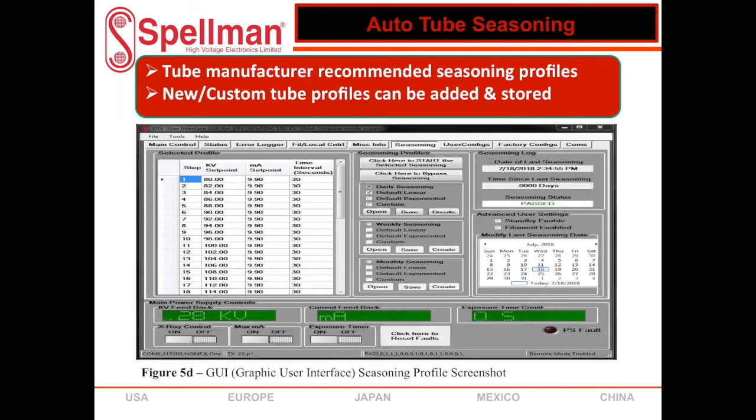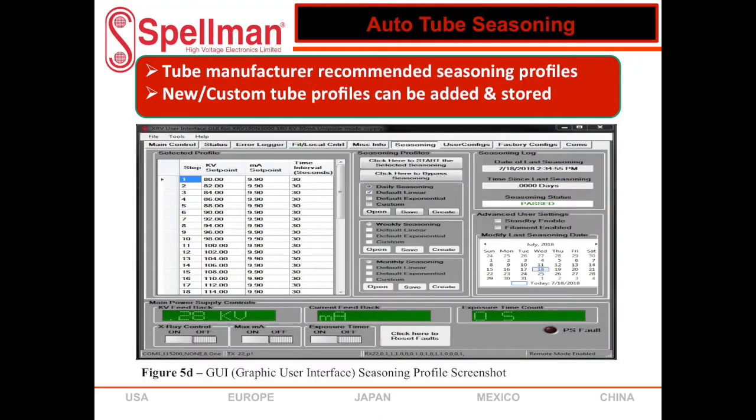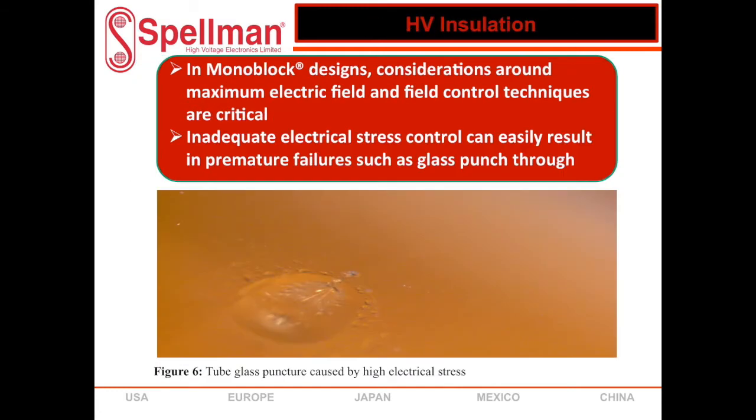Auto tube seasoning profiles are also a benefit of being able to download those tube settings. So you select the tube from the drop-down menu, and you get all the manufacturer recommended seasoning profiles, whether they be daily, weekly, or monthly. And then, of course, new and custom profiles can be added and stored, even for tubes that are already in the database. This section is more specific to monoblocks, the HV insulation.